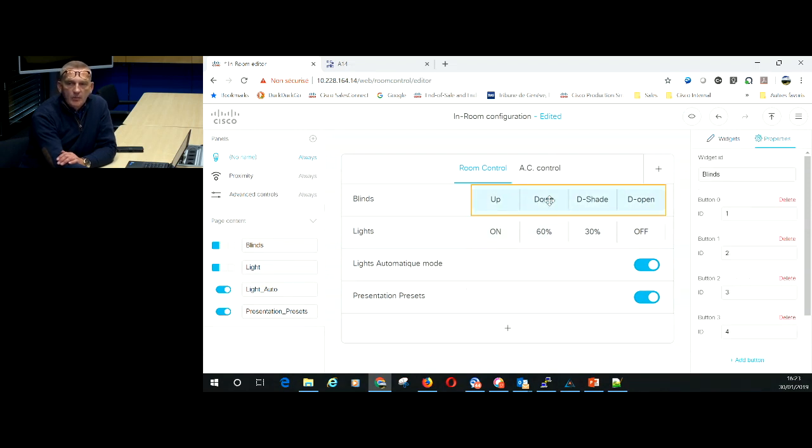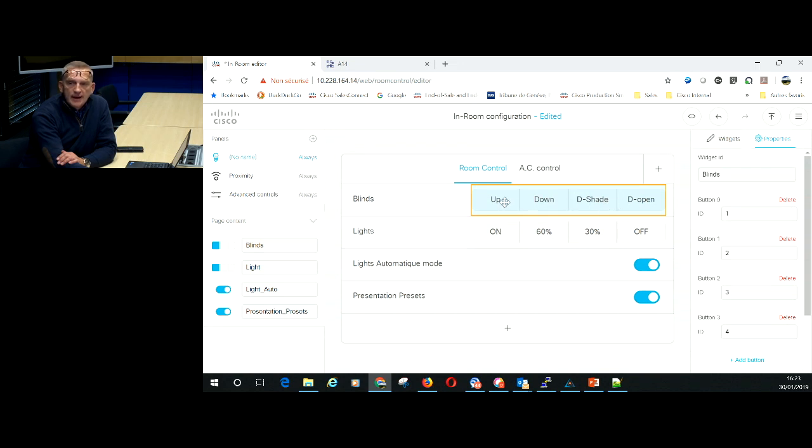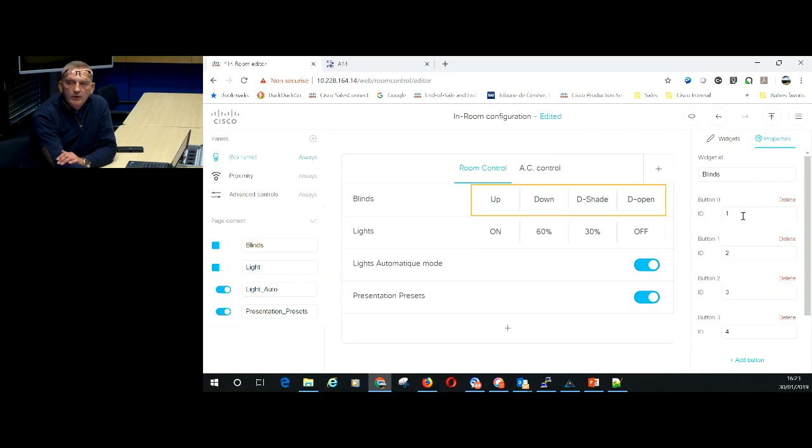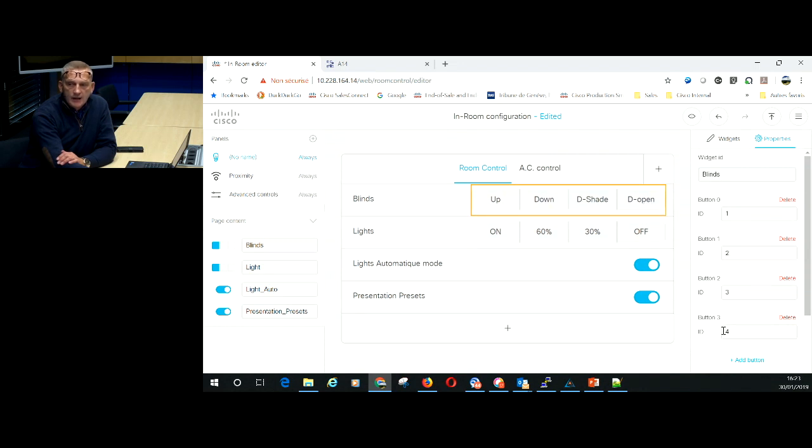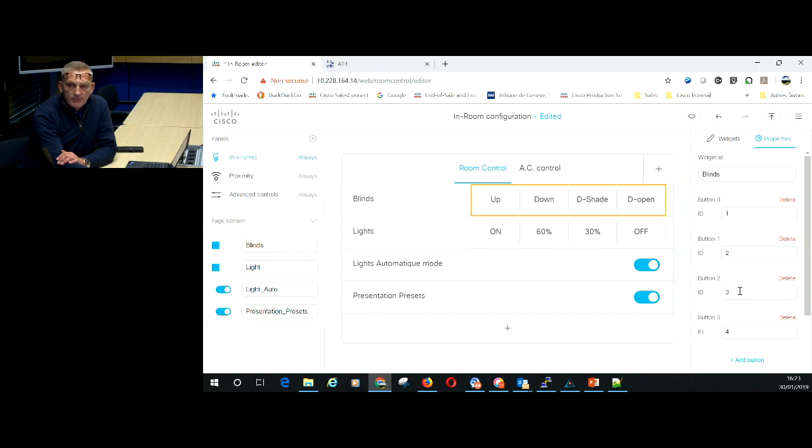So if I select blind command and the buttons that are associated to it you'll see that I have a group of four buttons. Under the widget ID I have a sub ID per button. The up is one, the down is two, downshade is three, downopen is four as an example. Those are the information that I'm going to use in my code to control the building management system.